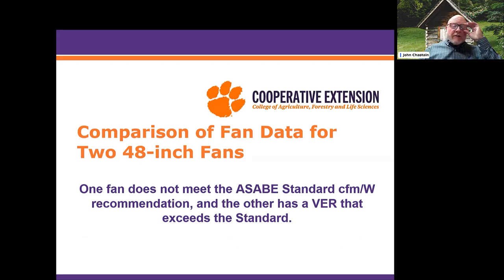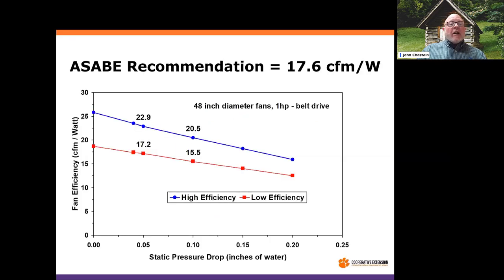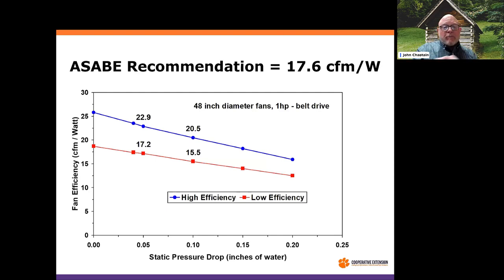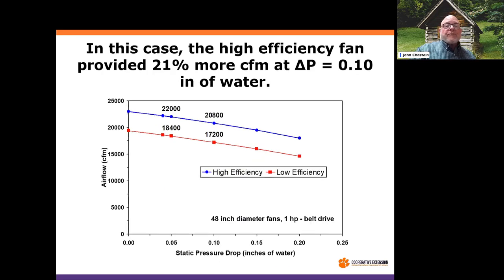Let's look at a quick comparison using two 48-inch fans — one does not meet the minimum ASABE standard for VER, and one actually exceeds it. The ASABE guideline says 17.6 CFM per watt at one-tenth of an inch static pressure is needed to consider a 48-inch fan energy efficient. The low efficiency fan on this chart shows 15.5 CFM per watt — well below the minimum. The high efficiency fan I'm comparing it to is 20.5 CFM per watt. We also see more airflow at one-tenth inch for the high efficiency fan: 20,800 versus 17,200 CFM.